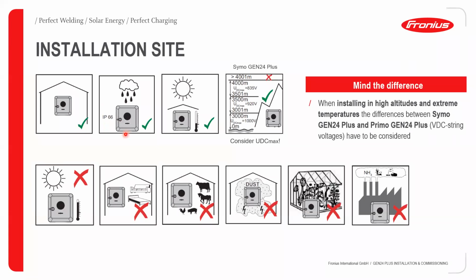So for installations, like I've said, it can be installed both indoors and outdoors, but we recommend that it be installed under shade. This, of course, helps the ambient temperature coefficient, because generally, for inverters installed outdoors, if temperature increases beyond certain limits, it will eventually affect their optimal performance. But the good thing is that our inverters can actually perform even at 50 degrees Celsius ambient temperature, thereby outperforming most inverters in the market. And of course, having said that, I must say here that all Fronius products are actually tier 1 products. We have recommendations that should be adhered to.